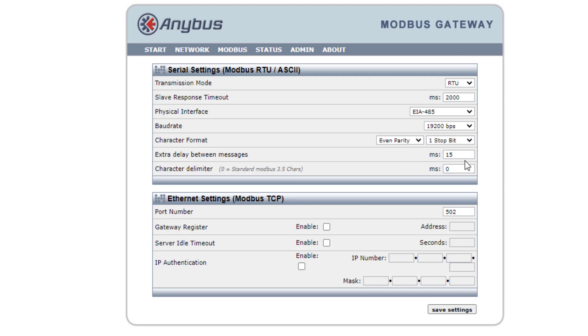This extra delay between messages is the interframe spacing. So you transmit your 16-bit word. There's no comma to distinguish between the end of that transmission. So what we tend to use is a transmission where nothing's happening. That's basically what that is, 15 milliseconds. That will prevent data overrunning into each other. And then down here your port number. This is really important.